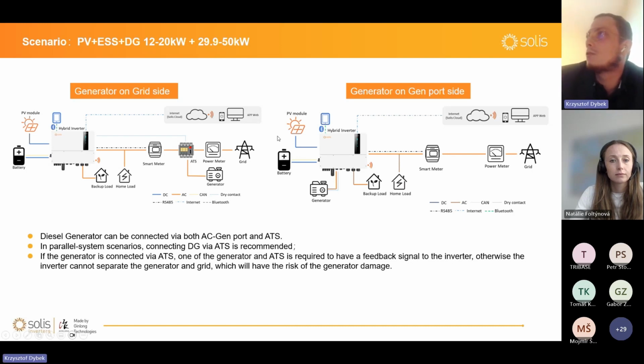Yeah, and we have two different versions of it. First is if you have a generator connected to the ATS near the main circuit breaker. In this scenario, the generator is still able to cover your backup load to charge your battery if the battery is drained, and your home load is still maintained, but you need to be extremely careful with commissioning of this hybrid inverter. Otherwise, the inverter will not know that the generator is on the AC side, and I can imagine that backflow power can damage the generator. It's not that common a scenario, but I am an electrician and I know that it's better to avoid troubles if you can. So it's better to make sure that everything is fully commissioned here in this hybrid inverter.